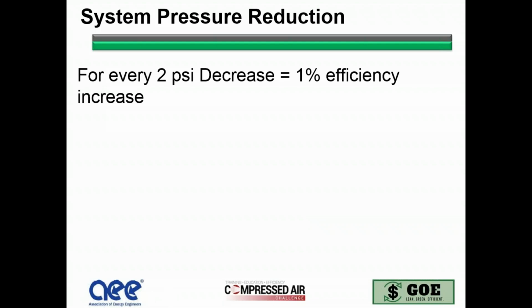So one of them I want to talk about, though, is system pressure reduction. For every 2 psi, it's a 1% efficiency increase. This can be converted back to bars, or to standard measurements that you have, but since a lot of the compressed air challenge material is based from the US, we do talk in PSI. But really, the importance is that reducing that pressure gives you the efficiency.